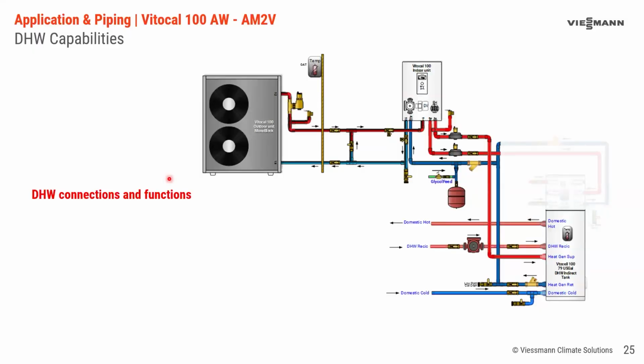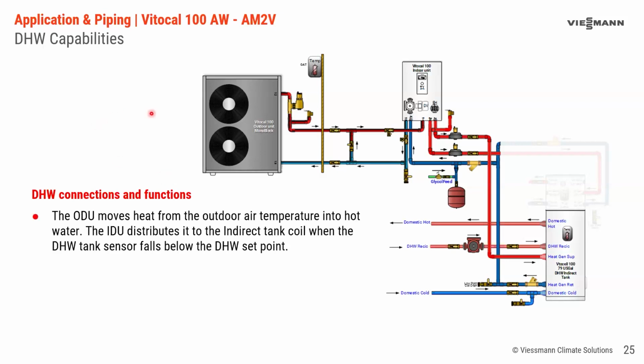Because we want to make sure that the bypass is blocked this way and open this way when the power is on the valve. Now, when we look at the DHW on its own, and there may be a possibility that this system is just DHW, right? Maybe this is what they've designed to do, and that's possible. I don't think we're going to see a lot of that, but it is possible. The indoor unit moves the energy from the outdoor unit as it heats the water up, because essentially it's in a heating mode, even in the summer. It's going to come through here, and it's going to come down to this line here to the indirect coil, and it's going to be based on the sensor that's in the tank. The sensor in the tank is connected to the indoor unit, and it's going to have a set point in the indoor unit for your domestic hot water. And when it drops below the set point, we're going to start up the outdoor unit.